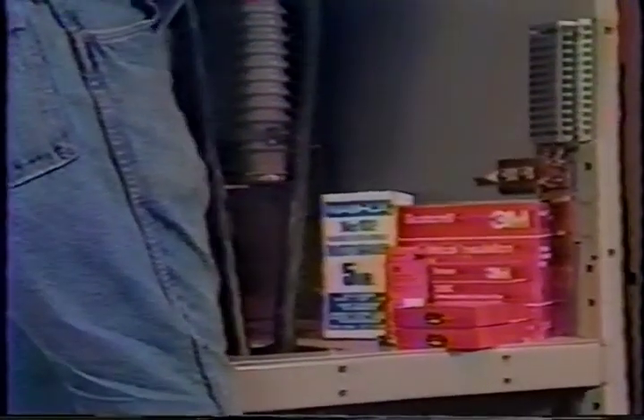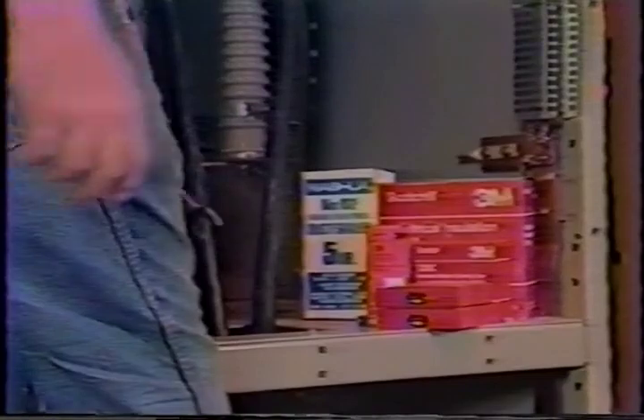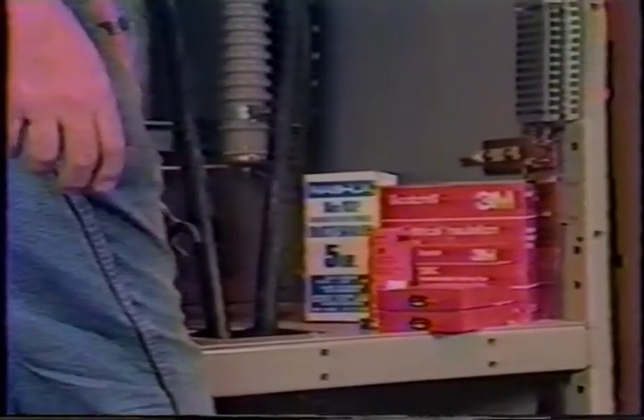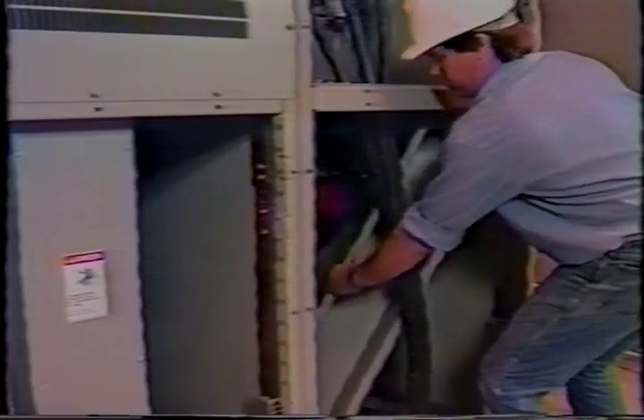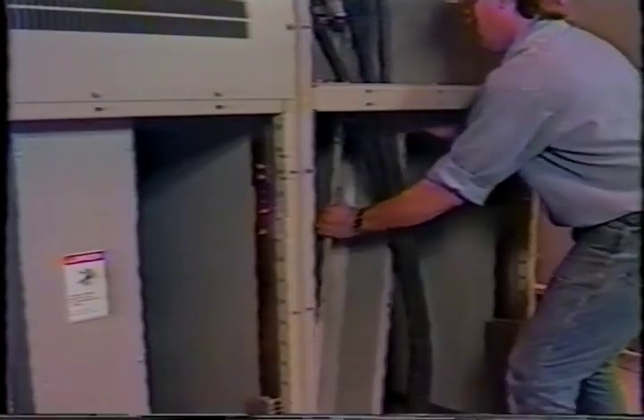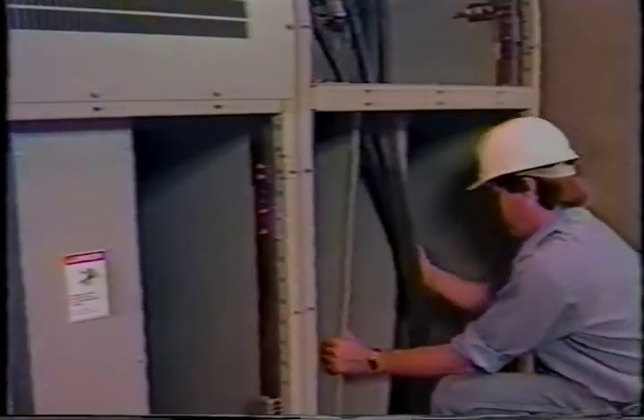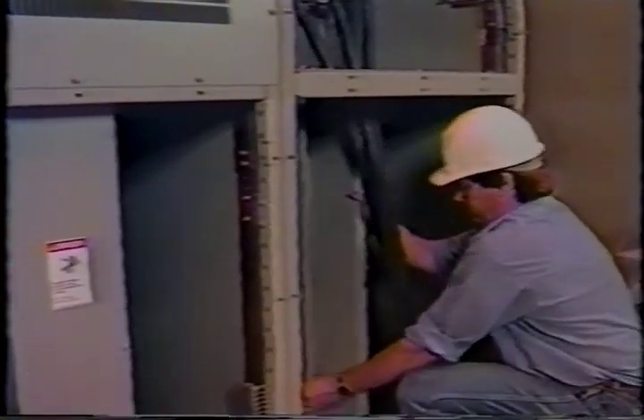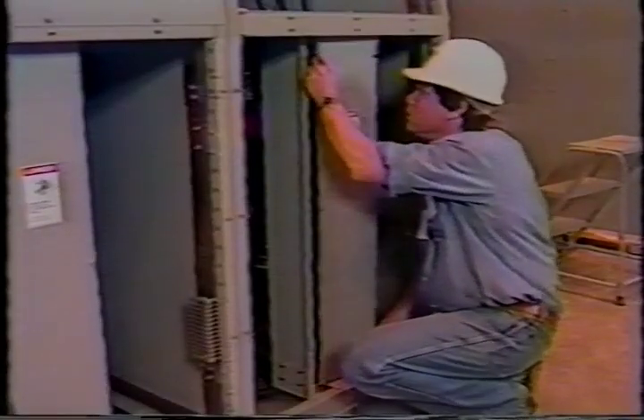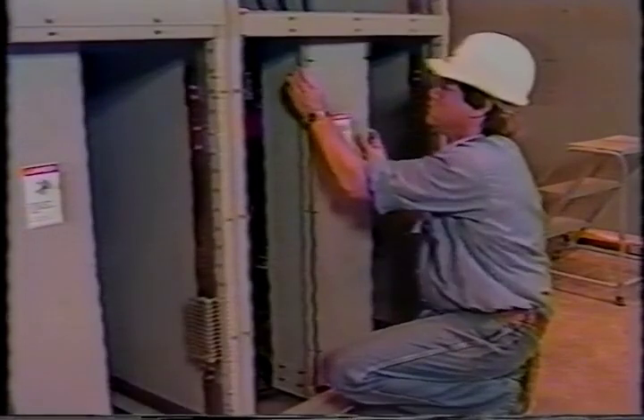Follow the instructions on insulating the joints so the insulation will taper properly through the correct gradient. The insulation will vary with the type and size of cable and with the service voltage for which it is designed. The troughs should be reassembled after cable installation is complete. Replace the rear covers on all the vertical sections.